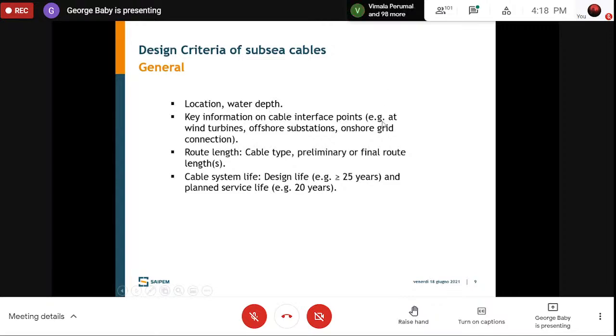And the other key information to design an offshore subsea cable is the type of termination, where we are connecting this cable, whether it's to an offshore substation, an onshore substation, an onshore grid, an onshore switchyard or a wind turbine. The termination point will vary and the connectors will be designed accordingly.